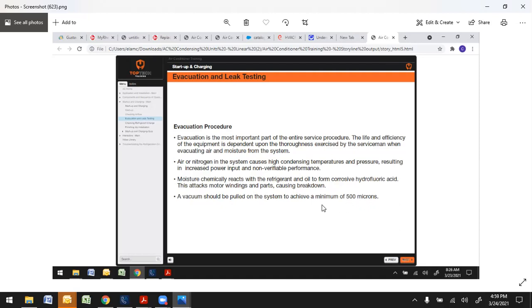They don't go into great detail here about a triple evacuation. Years ago, I started doing a triple evacuation on every service call, every time I put in a unit, anytime I opened up a system. It may have taken me an extra 15, 20, 25, 30 minutes. But when I left there, the system was clean, it was dry, and the odds of me having to come back for moisture, non-condensables, or a leak was non-existent. It's much cheaper to spend the extra 15, 20, 25 minutes, even an hour, than to come back on a callback for leaks that were missed or non-condensables.